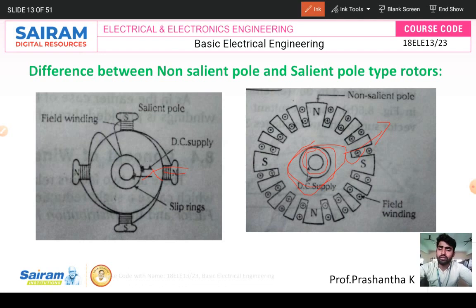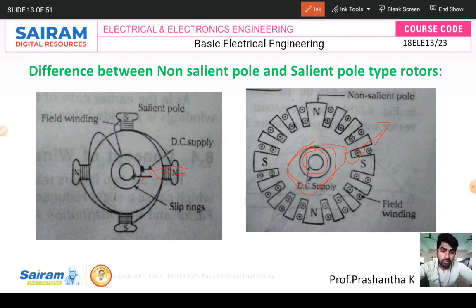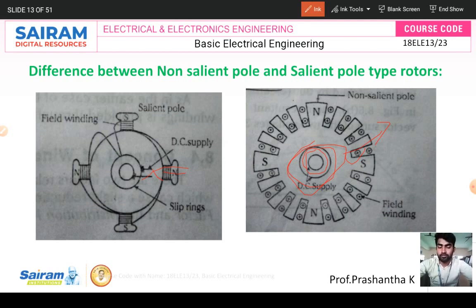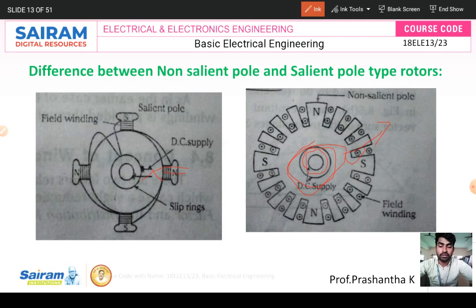In the non-salient pole rotor, it is used for turbo machines like turbo generators because the speed is more. In the salient pole rotor, the poles are projected out from the surface. In the non-salient pole rotor, there are no projected poles — the unslotted portion is called poles. So the salient pole is a projected pole synchronous generator, and the non-salient pole is a non-projected pole synchronous generator.